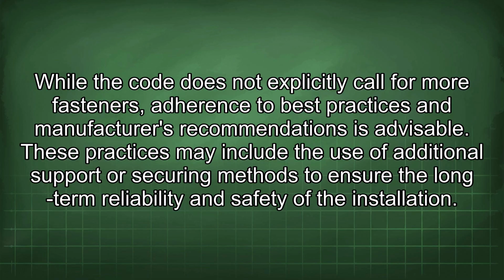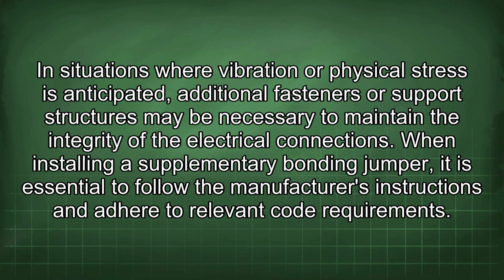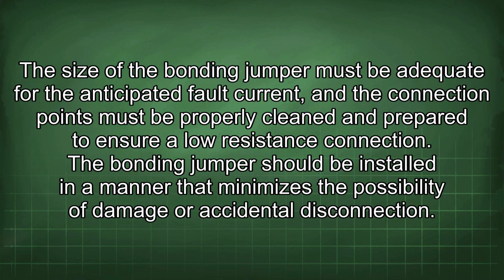the installation. In situations where vibration or physical stress is anticipated, additional fasteners or support structures may be necessary to maintain the integrity of the electrical connections. When installing a supplementary bonding jumper, it is essential to follow the manufacturer's instructions and adhere to relevant code requirements. The size of the bonding jumper must be adequate for the anticipated fault current, and the connection points must be properly cleaned and prepared to ensure a low resistance connection.